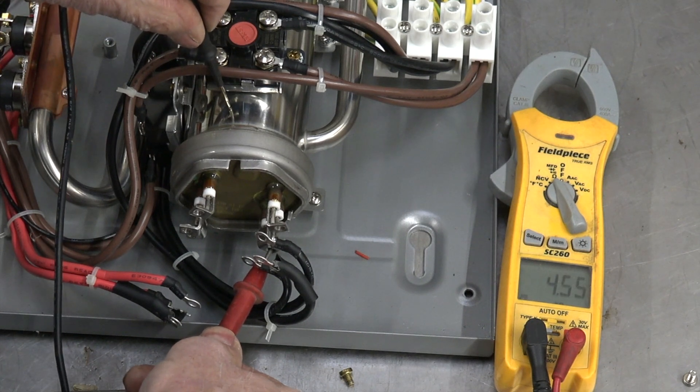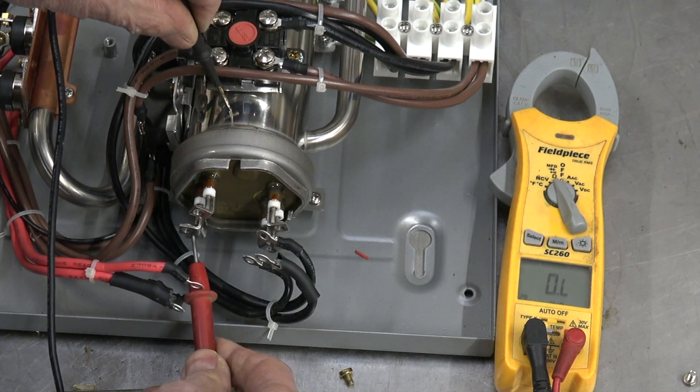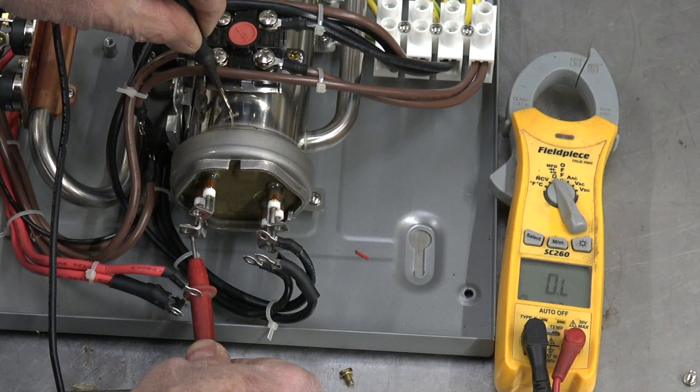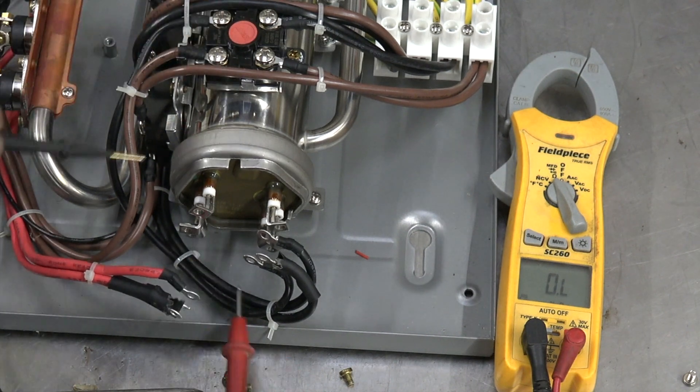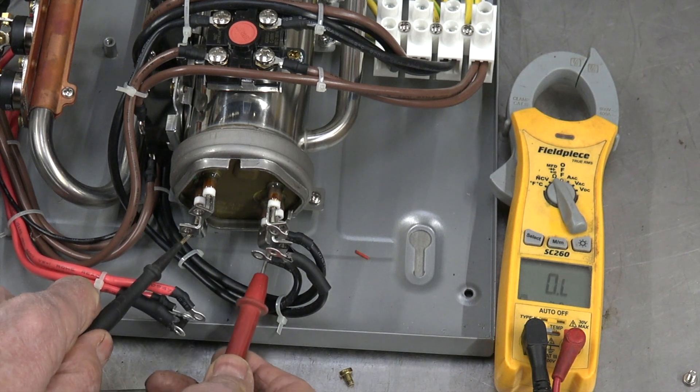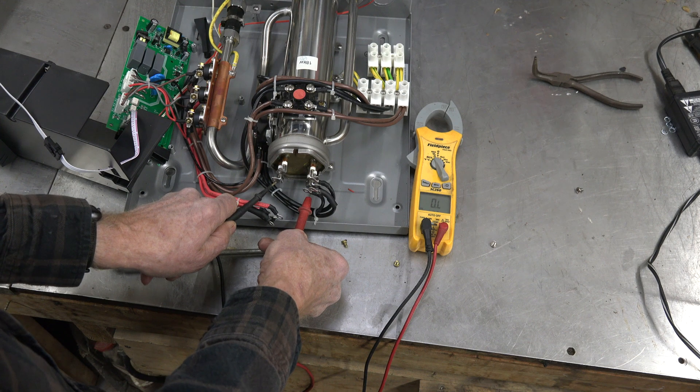Let's go to the bottom one. We have continuity to ground on that side. Here we have continuity - no, we don't have continuity at all. That element is broken. So when I go here across this element, I'm going to read OL.